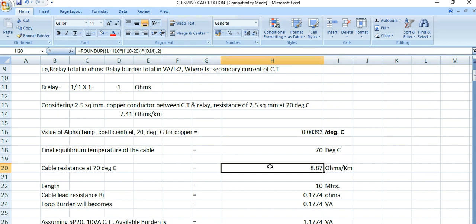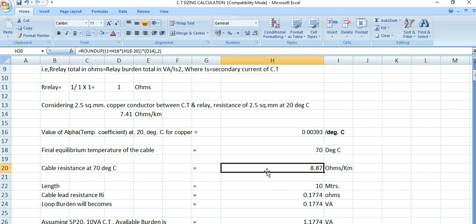The formula used is: R2 = R1 × (1 + α × (T2 − T1)). Here, alpha is the temperature coefficient of copper = 0.00393, T2 = 70°C and T1 = 20°C, and R1 = 7.41 ohms/km. Applying this formula gives 8.87 ohms per kilometer — this is the cable resistance at 70°C.